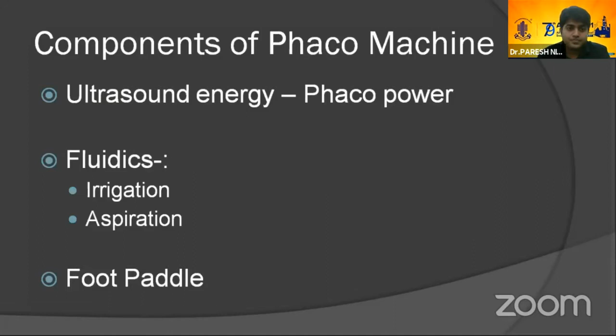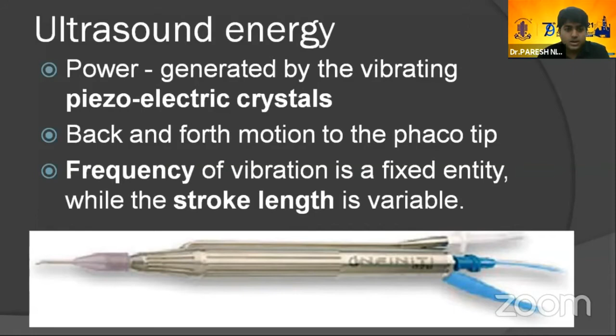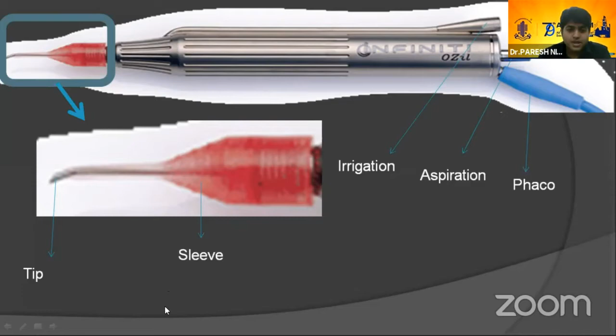If we talk about the ultrasound probe, it gets its energy from the vibrating piezoelectric crystal, which moves the phaco tip back and forth, creating a jackhammer effect. The frequency of each individual handpiece is fixed depending on the company and the phaco handpiece, while the stroke length can be variable depending on the settings which we set. If we talk about the components, we have one irrigation port, one aspiration port, one port for delivering the phaco energy, and the tip is covered by the sleeves. We have different tip sizes and sleeve sizes.